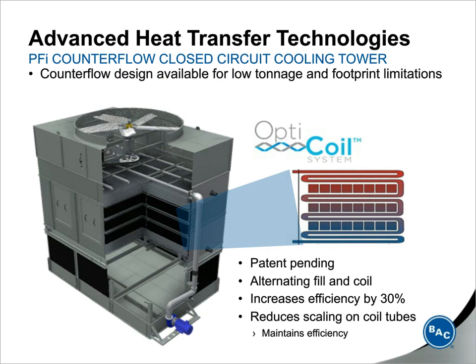In 2015, BAC actually introduced a new heat transfer technology. It's only available for counterflow cooling towers, or closed-circuit cooling towers. This design includes fill that's actually nested between coil rows, and it increases thermal efficiency over traditional counterflow closed-circuit designs by as much as 30%, while still offering dry performance for buildings that do benefit from operating dry during the winter. Now, again, the crossflow design is still more energy efficient. It offers a lower total cost of ownership than the counterflow design. But this particular counterflow design offers a benefit that's very similar to what crossflow offers.